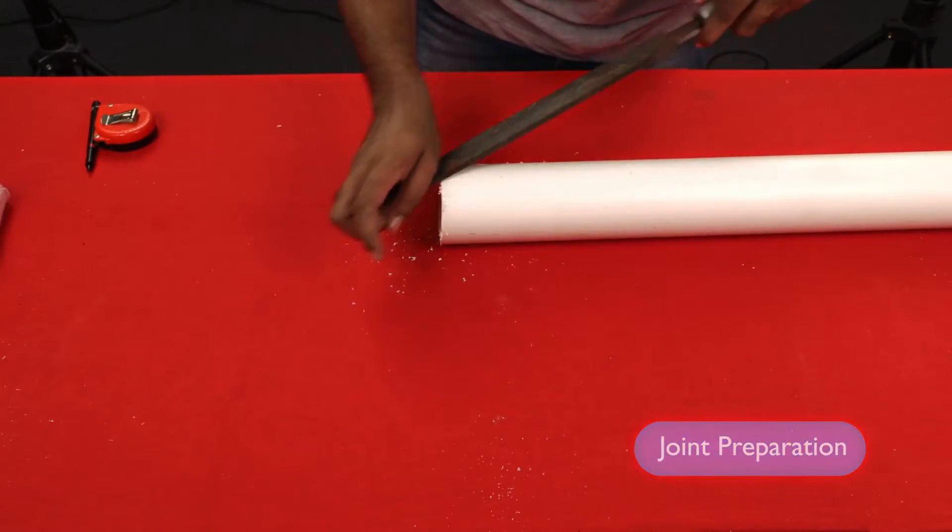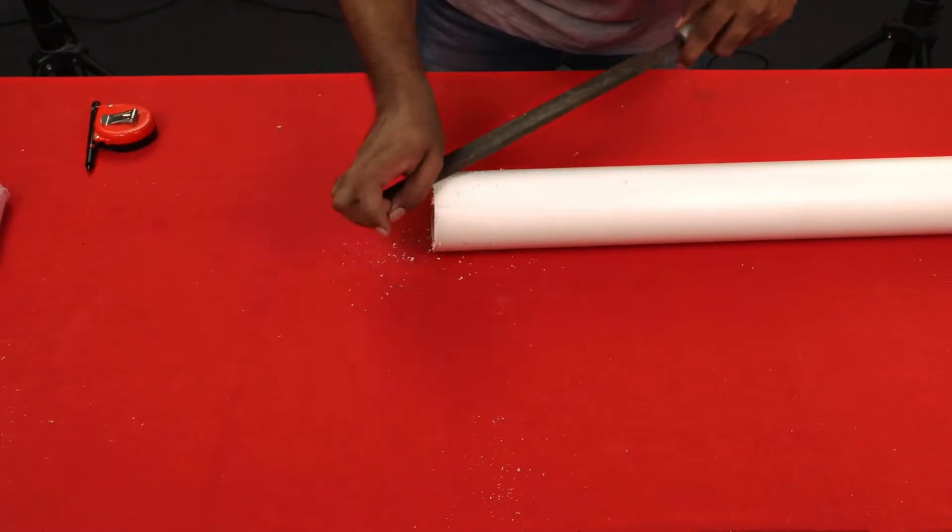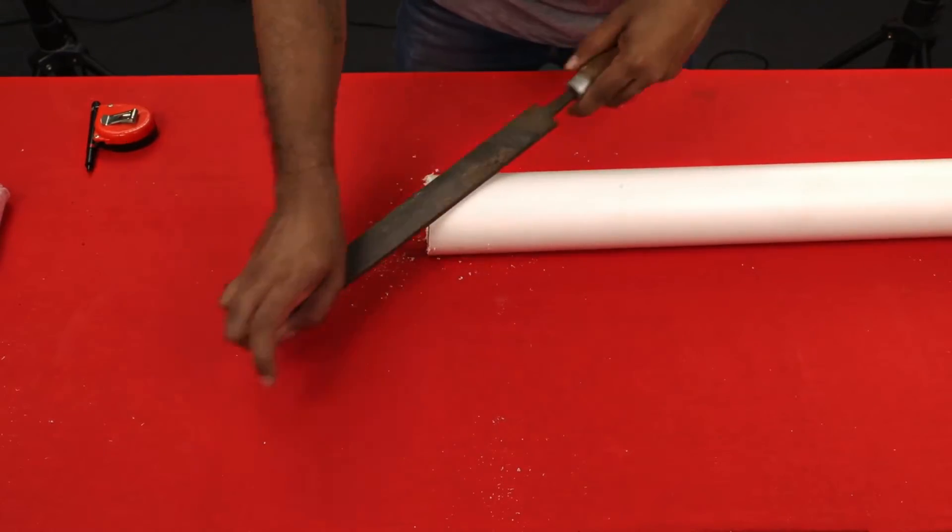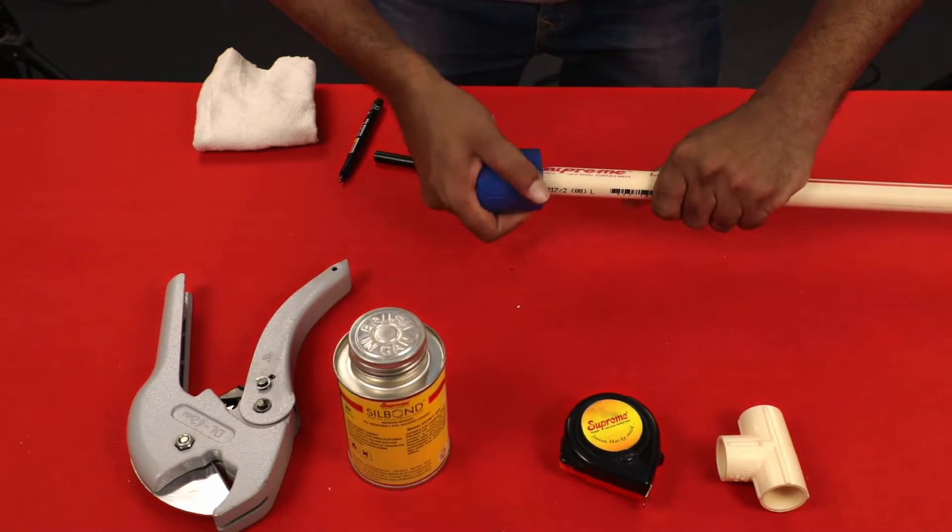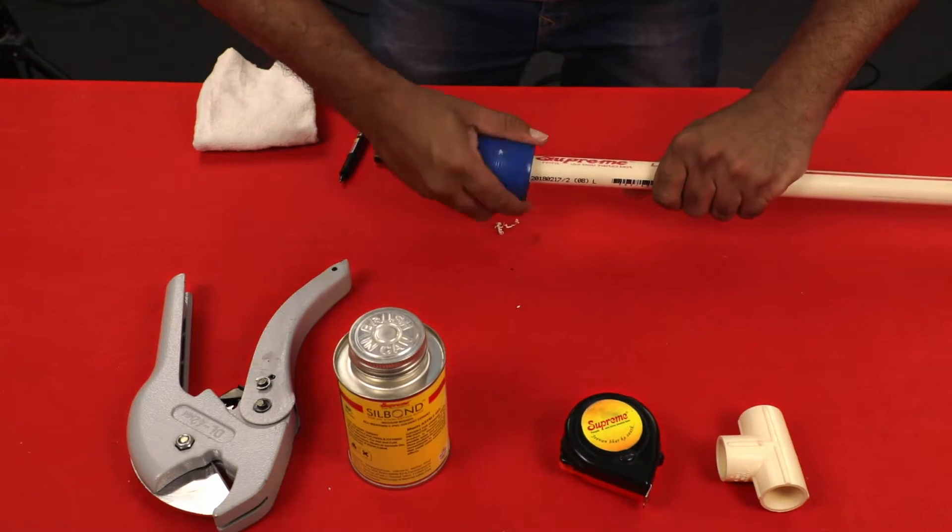Joint Preparation: Chamfer or deburr pipe or both, approximately at 10-15 degree angle. Remove burrs from both inside and outside surfaces.